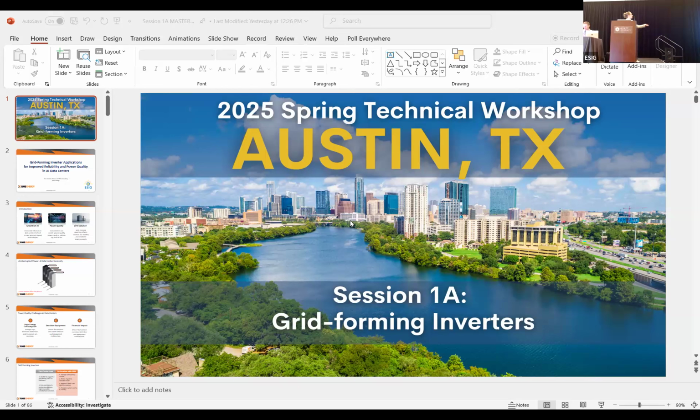So in this plot, I have an example of a meter failure. Anything could happen. The meter could be MIA, maybe there's a PT failure, and we have defined responses for those events. In this example, once that meter failure is qualified, the plant in this case was configured to ramp down in a defined time interval. So both P and Q reach 0 at the same time.